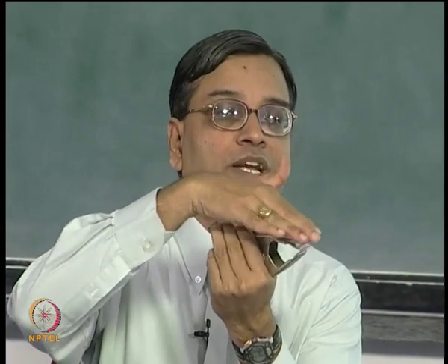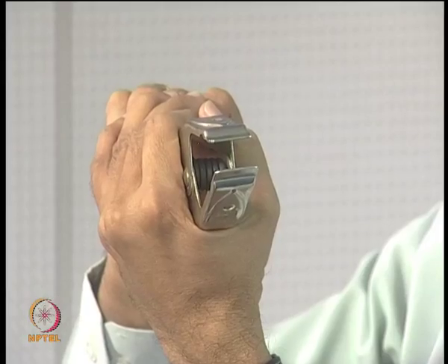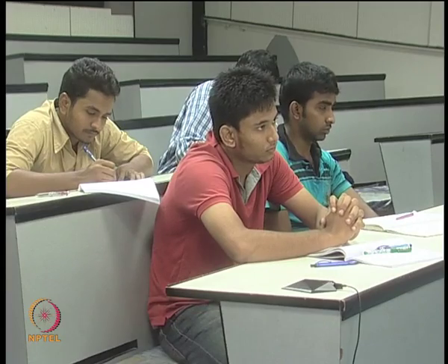You will have a sort of a wood piece and then a gauze, so that whatever the pressure that is developed, that is evenly transmitted to the strain gauge, and you have this available with a ready made spring whose stiffness is suitably adjusted to give the desired pressure. And this is for applying some pressure, and when I go for higher pressures, you also have a bigger system. It is very hard to press, I am really trying hard to press it. So, you can imagine I clamp it and put the whole thing in the furnace, so that you will maintain that pressure for polymerization to be complete. So, it is very detailed, strain gauge pasting is not a simple task. A person needs to be trained in strain gauge installation, and only when you make the installation as good as possible, you are guaranteed of the final measurement.